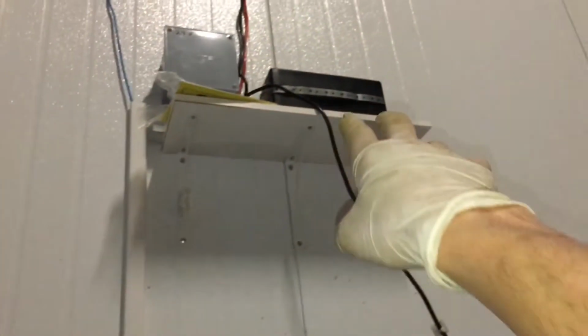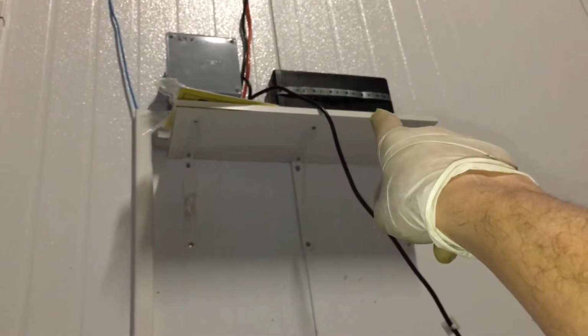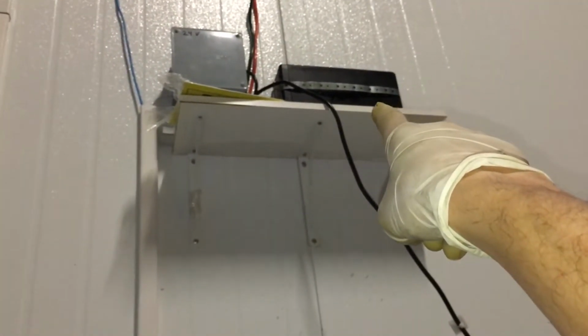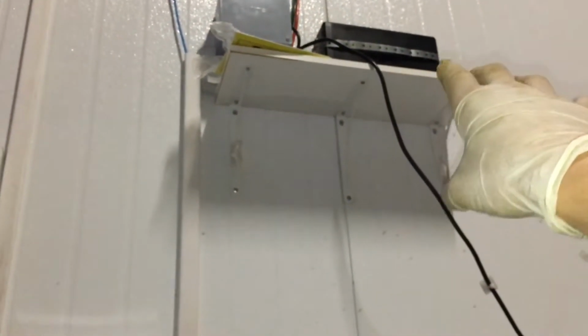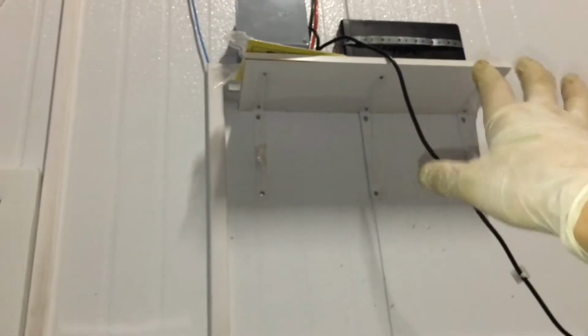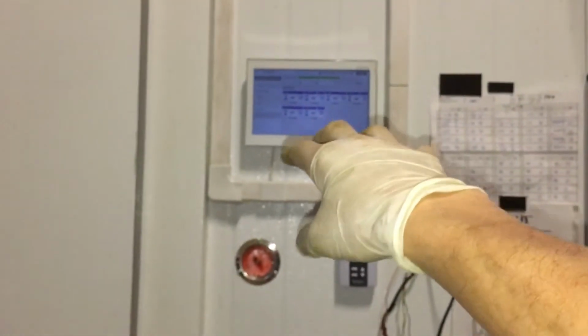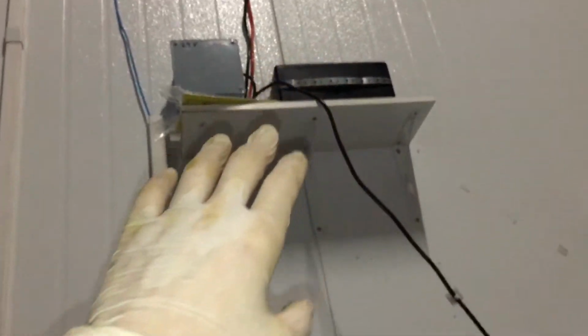But what you're seeing on the sensors over there are on the sensors here basically. And like I said, that's our voltage spike and battery backup right there to protect this system from any voltage spikes, or if power goes down temporarily, this doesn't even get interrupted. It doesn't even know when power goes out. I could unplug it and the system will stay up and running. That is also providing the voltage spike suppression for the monitoring system that is located over here.